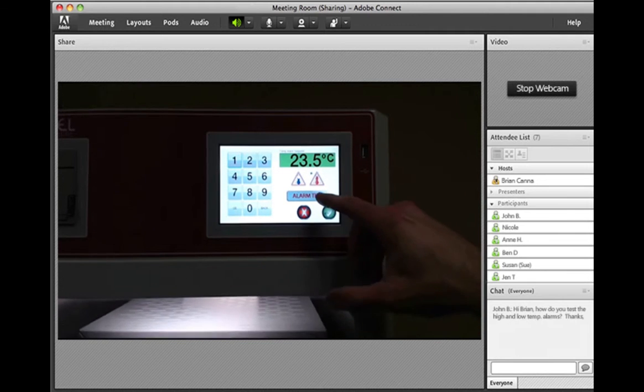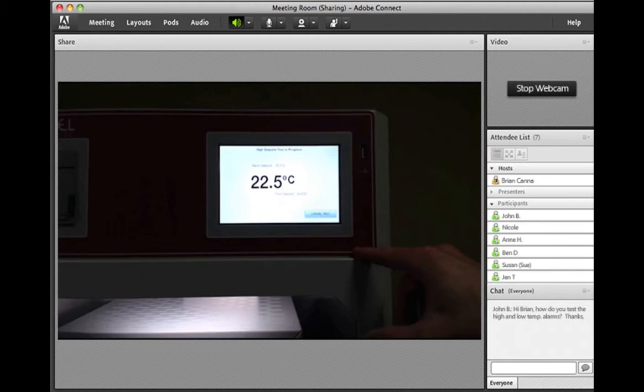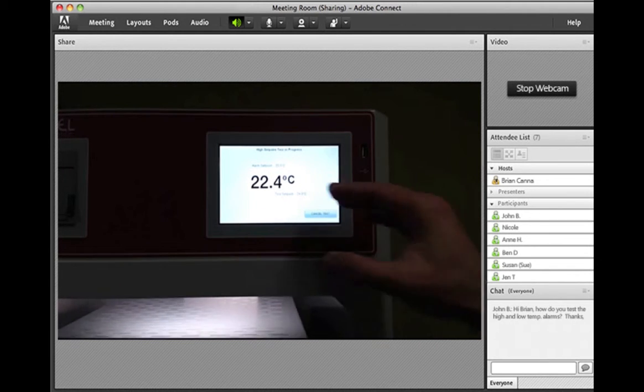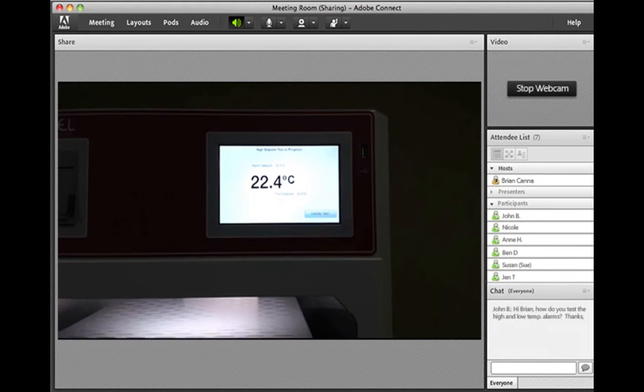So we'll test the high alarm first. We'll hit alarm test. And actually what it's going to do, it's going to run the temperature of the unit up to 23.5 degrees C. So it's going to be putting voltage into that Peltier to add heat into the system. As it does that, it will approach that alarm set point and it will alarm, and then that's proof positive that if your unit goes above that 23.5 degrees C, it will alarm in time. So I guess we'll just give it a couple minutes here. Now it may take a second to heat up because the PID control of the system is tuned so it can maintain that temperature at 22 degrees C.